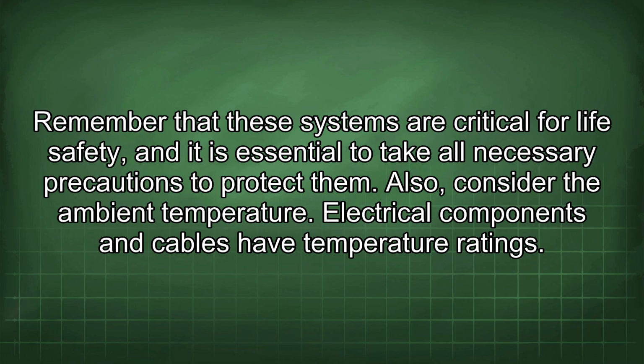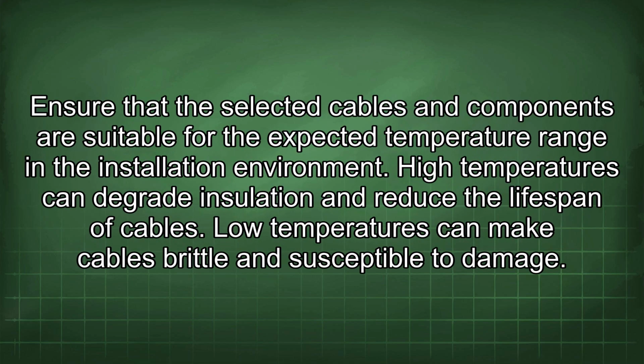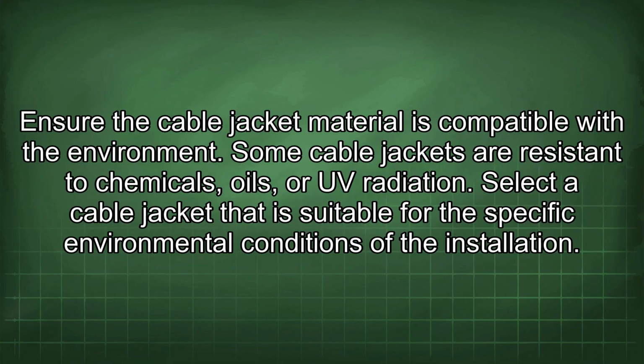Electrical components and cables have temperature ratings. Ensure that the selected cables and components are suitable for the expected temperature range in the installation environment. High temperatures can degrade insulation and reduce the lifespan of cables. Low temperatures can make cables brittle and susceptible to damage. Ensure the cable jacket material is compatible with the environment. Some cable jackets are resistant to chemicals, oils, or UV radiation. Select a cable jacket that is suitable for the specific environmental conditions of the installation.